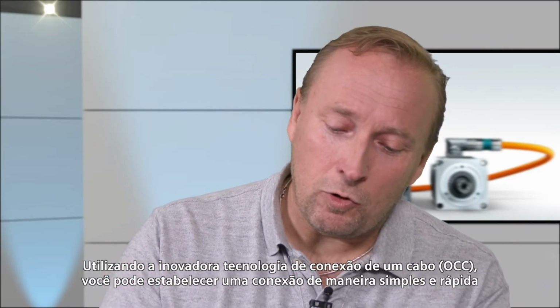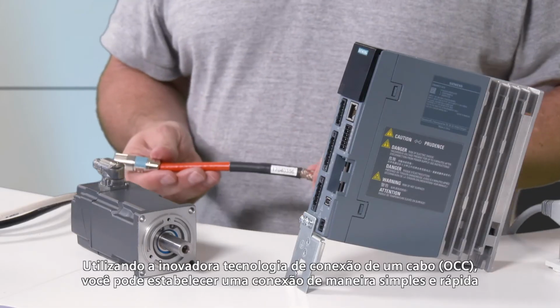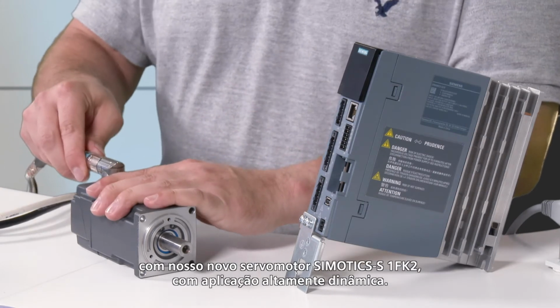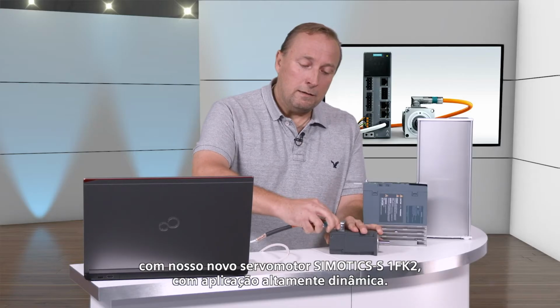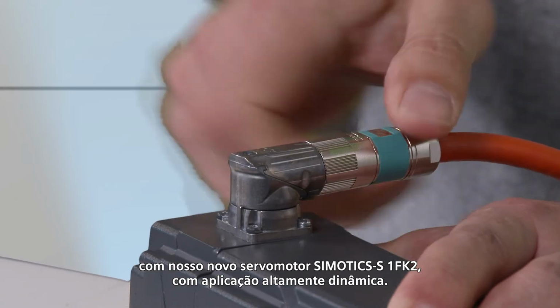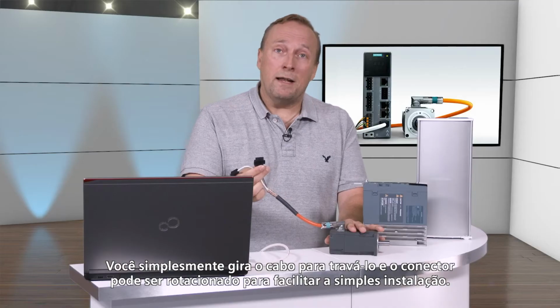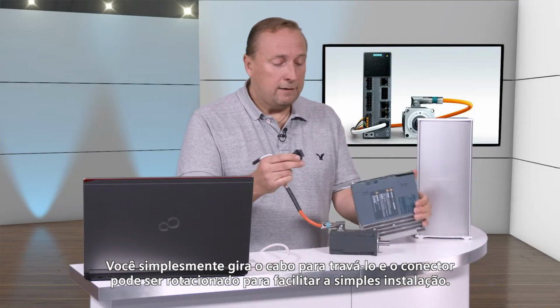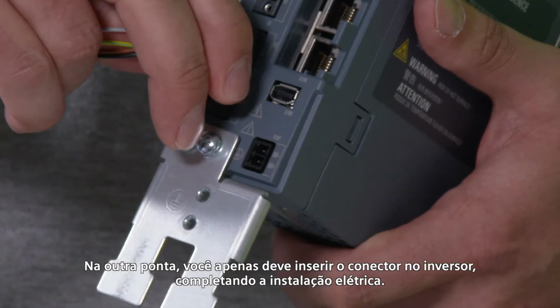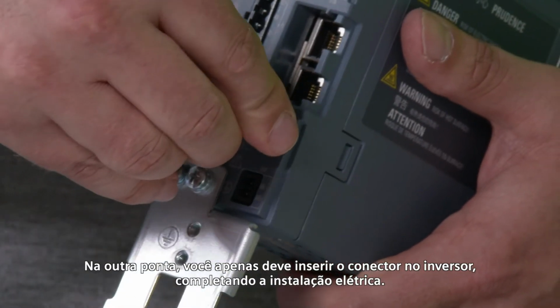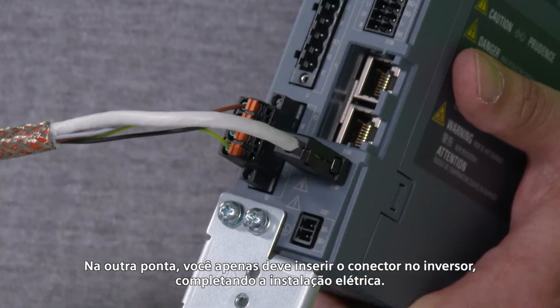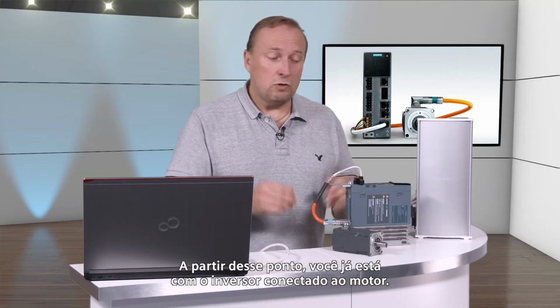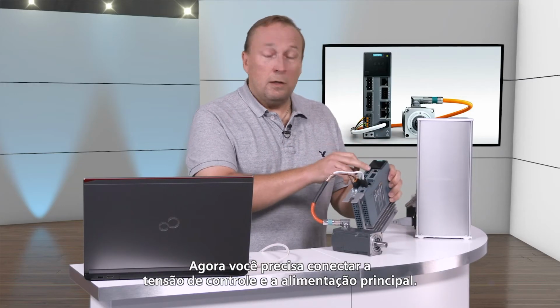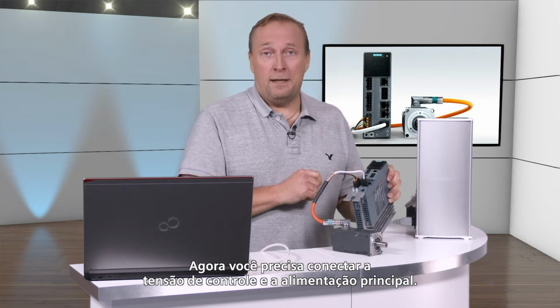Using the innovative one-cable technology, you can quickly and simply establish a connection to our new SIMOTICS S-1FK2 servo motor with a high dynamic performance. You simply turn it to latch, and the connector can now be rotated to facilitate simple installation. On the other end, you just have to insert the cable into the converter to complete the electrical installation. With this step, you have already connected the converter to the motor. You now have to connect the control voltage and the main power voltage.